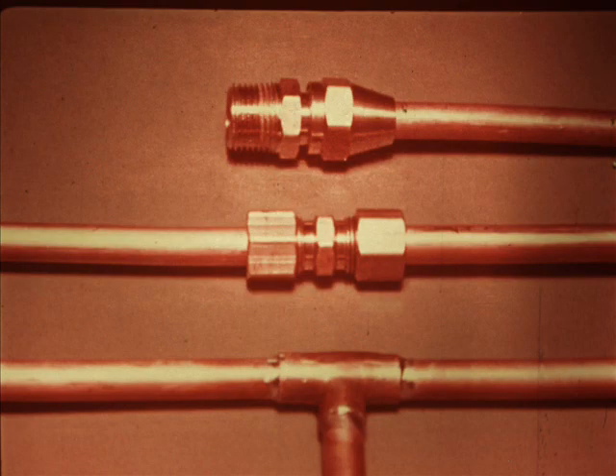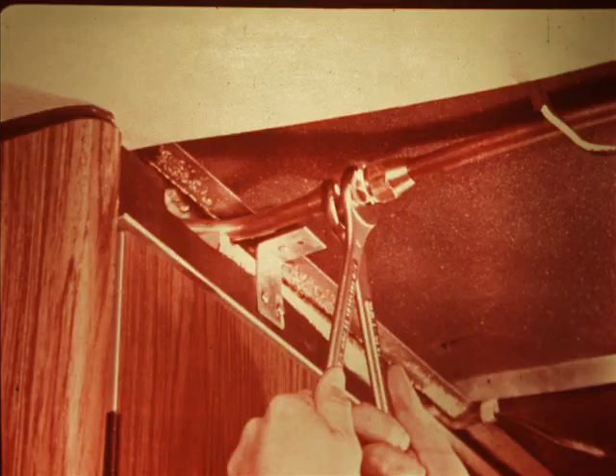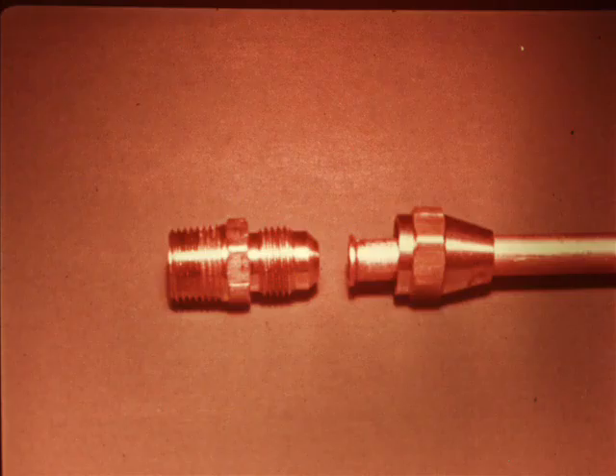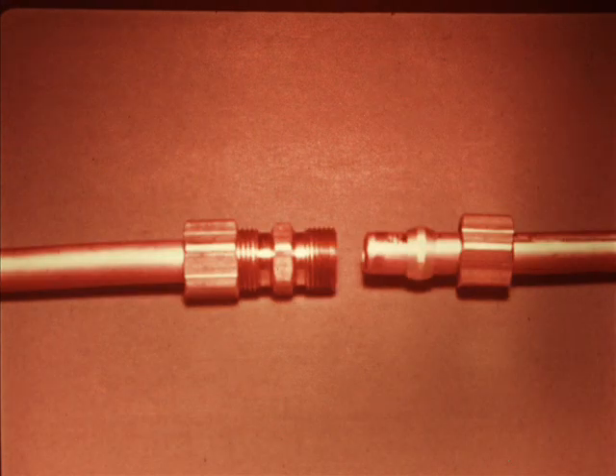The plumbing system contains 3 types of fittings: flared, compression, and sweat fittings. Each is repaired differently in the event of a leak. You should be able to correct a leak at a flared fitting by tightening the nuts. But if you can't, disassemble the fitting and check it for a crack or distortion. You'll have to connect a new fitting if the original one is damaged. If there is a leak at a compression fitting, it is likely that the fitting is defective, in which case you should install a new fitting.